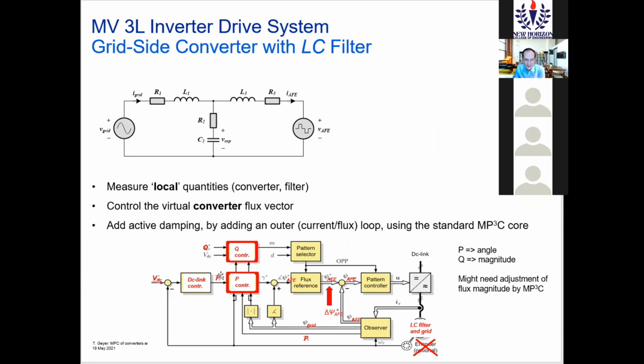Now you do exactly the same thing, it's just that this controller would control not the speed, but the DC link power. So you would have the DC link voltage reference, the measured DC link voltage coming from your converter. That tells you the power you should draw, the active power. You control your reactive power, and you do that by changing the amplitude of your voltage, so maybe your modulation index.